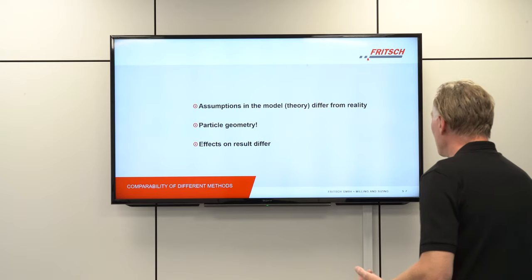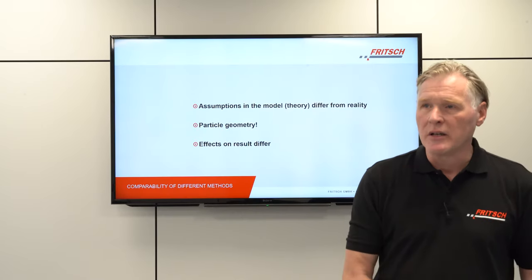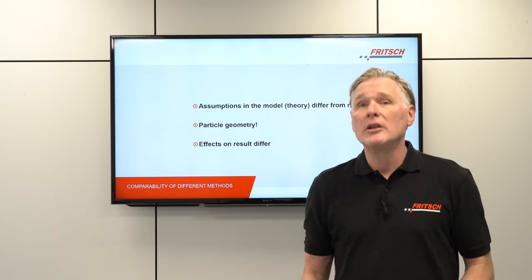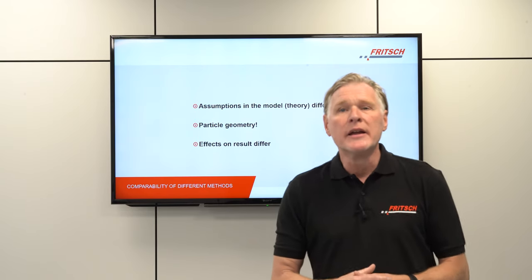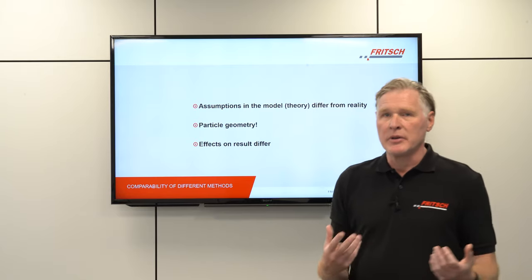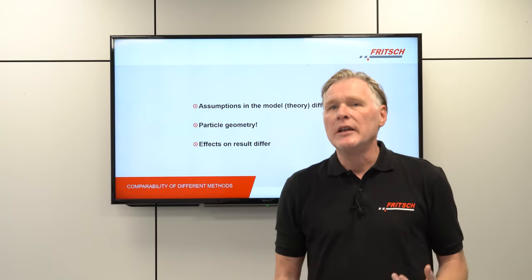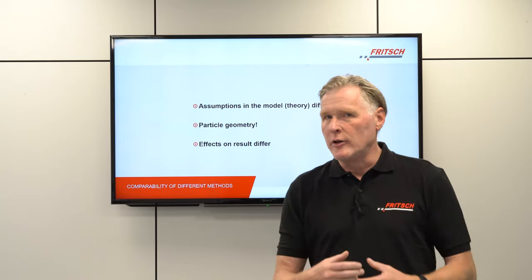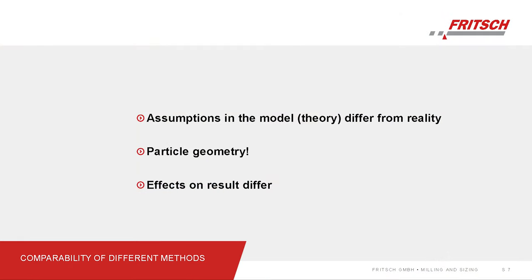The simple reason for this is that all those theories use models and assumptions that typically do not fit reality, so you have some deviations between the model and the real measurement situation. One important factor here is particle shape. Whether you have a spherical particle or a totally irregular shaped particle will strongly affect sedimentation, the scattering of light, or any other physical property you may observe.